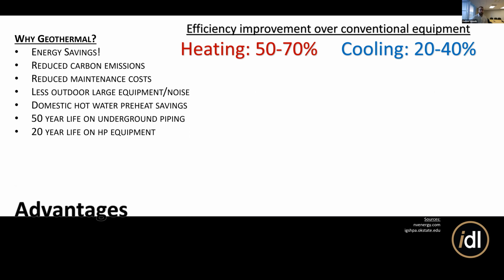Also, you've got lower maintenance costs. Because we are dealing with a ground system, and we've got in place our heat exchanger, the compressor doesn't have to deal with the high variations in outdoor air temperature, or even be set outside. It could be in a garage or sheltered in some way, because we don't have to be pulling that heat in from the air. Instead, it's just going to be going through that heat exchanger. So that means that outdoor compressor is going to last a lot longer than a traditional airside system would.